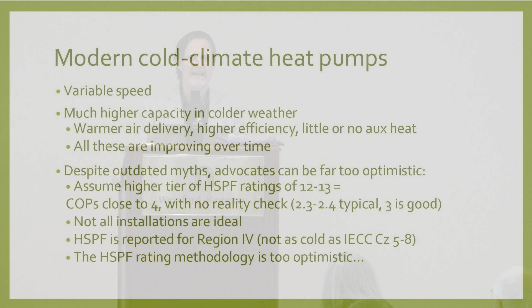An HSPF of 12 to 13 is in the range of a COP of 4. And I have yet to measure a heat pump operating in New York, New England, or any similar cold climate that has an operating COP across an entire winter anywhere near 4. Well, yeah, 2.8 was mine, right?